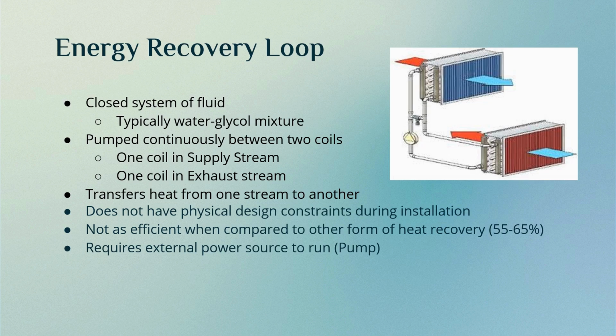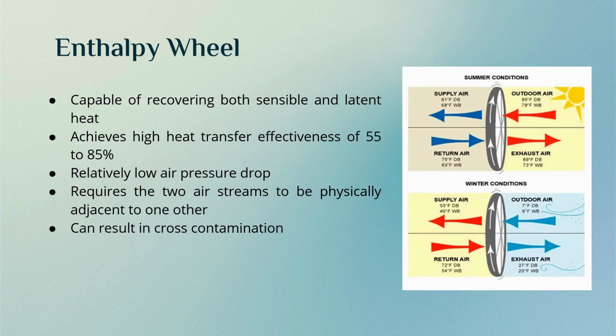This equipment does not have any physical design constraints during installation. However, it's not as efficient compared to other forms of heat recovery and does require an external source of power to run. The second piece of equipment we looked into was an enthalpy wheel, which is capable of capturing both sensible and latent heat with a high heat transfer effectiveness and relatively low air pressure drop. However, this system does require the two air streams to be physically adjacent to one another and can result in cross-contamination.